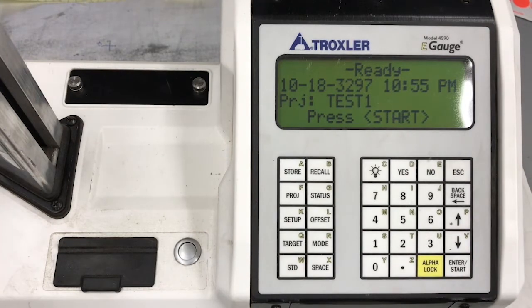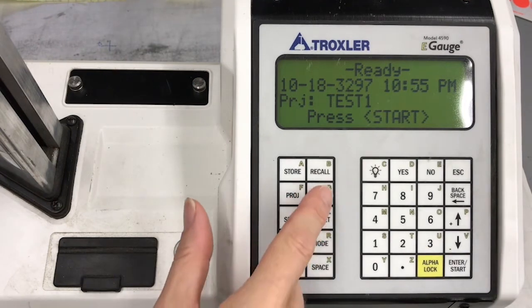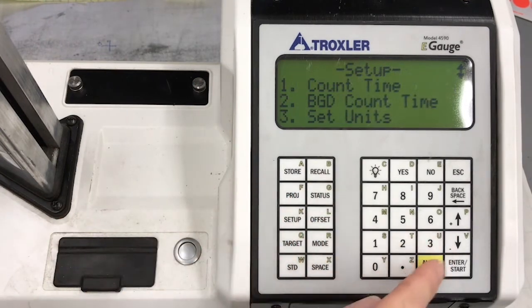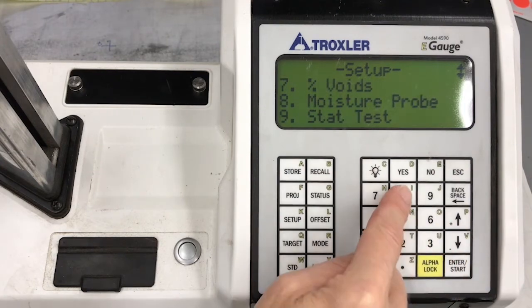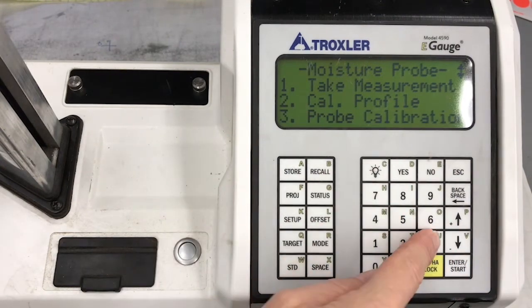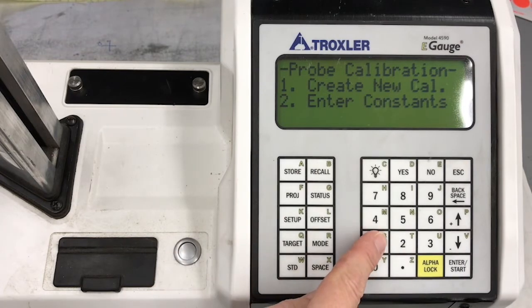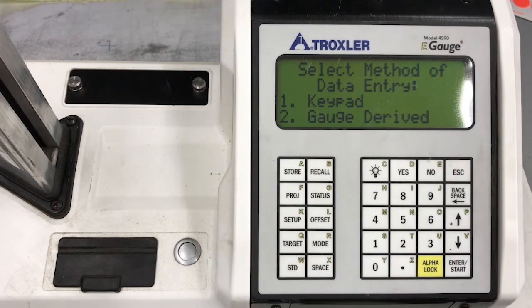The other option for correcting the moisture readings is a moisture probe calibration, which is accessed under the Setup menu, under Moisture Probe, which is number 8, and then Probe Calibration is number 3, Create a New Calibration is number 1. You can either do keypad entry, which is what we will do in this example, or gauge derived, which means you will take the readings in the field, store them as a partial, and then bring your samples back into the lab to dry them and enter that data later. So it's your choice which one to use, but we're going to use keypad.